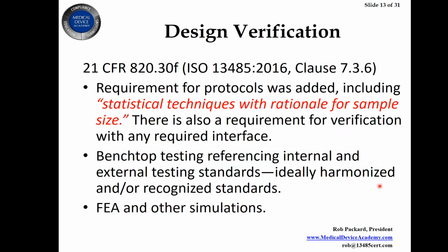process. Any benchtop testing you're doing, a lot of the external testing standards, harmonized standards, recognized standards, those are all verification for the most part. And if you do FEA, which is finite element analysis, or other simulations, particularly in software, these things are going to be all verification activities. You also want to make sure all of those are included in your design inputs.